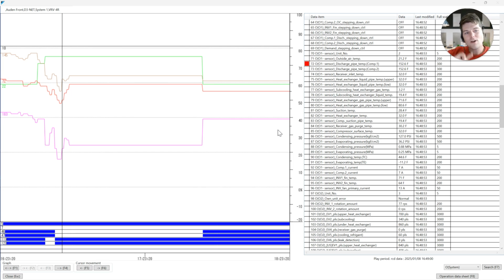But also, what does it look like when it defrosts a second time after giving away all its heat? Does it build back up like it's supposed to, pretty quickly? And the answer is no, it doesn't. Now, it does get there over time, so I do have to give it to the little steam engine that could. It did chug away until it got there. However, it still took an hour to defrost this coil, which is one of two things. Again, refrigerant charge, which is what I'm leaning towards, or we could also have faulty sensors or sensors that are misreading, that would cause it to run this long because it thinks that there's still ice when maybe there's not. All right, that is a long tangent on defrost.